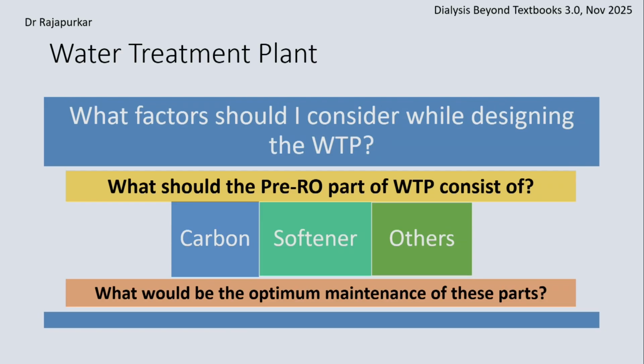Softener, if it is a situation like mine, in the previous unit, we added a softener before the 3-column DI, because that way my resins' regeneration requirement goes down. Not so much as it is absolutely needed to get rid of it. In the present system, what we have done is we have got 2 ROs in series followed by electric DI. So you polish off the remaining with an electric DI and you completely obviate the need for acid and alkali there.